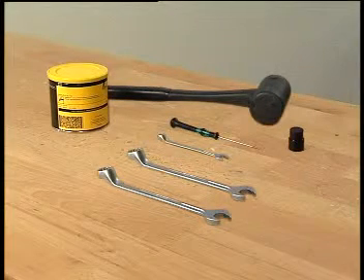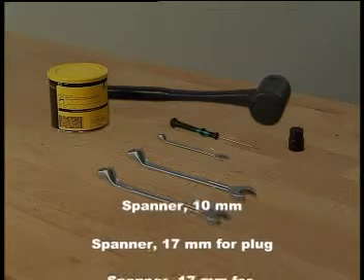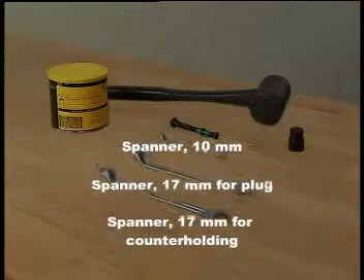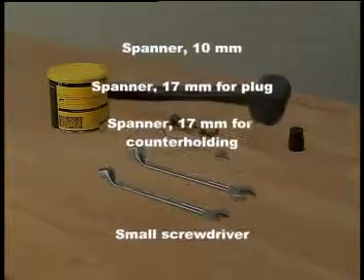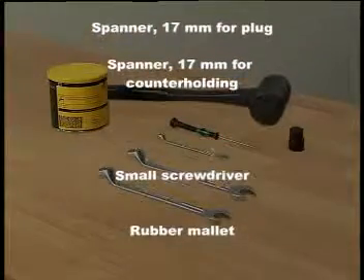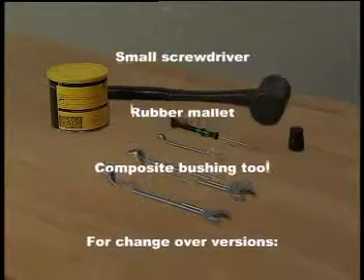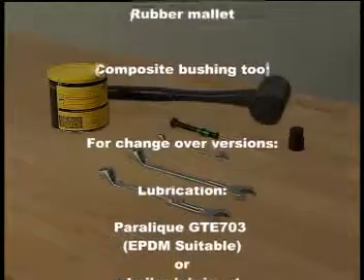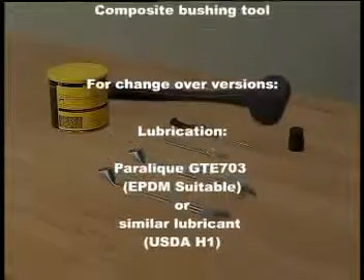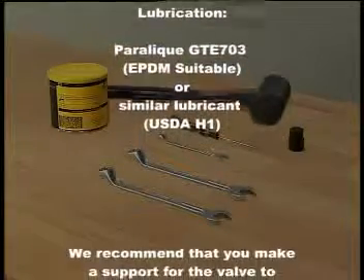The tools shown here are those required for rebuilding the unique SSV valve into an aseptic version: spanner size 10 for the clamp, spanner size 17 for the plug, and spanner size 17 for counter-holding the actuator stem. A small screwdriver for releasing the air behind the plug seal if the plug is not ordered with the seal mounted, and a rubber mallet for the composite bushing tool. For changeover versions, lubrication Paralique GTE703, EPDM suitable, or similar lubricant, USDA H1.